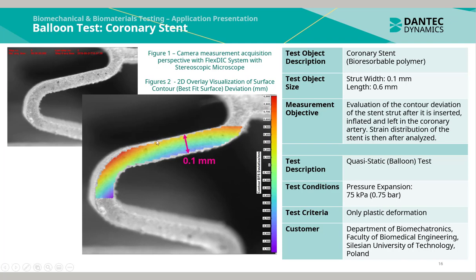The stent itself is approximately 0.1 mm in width and 0.6 mm in length. The measurement objective is to evaluate the contour deviation of the stent strut after it has been inserted, inflated and left in the coronary artery.